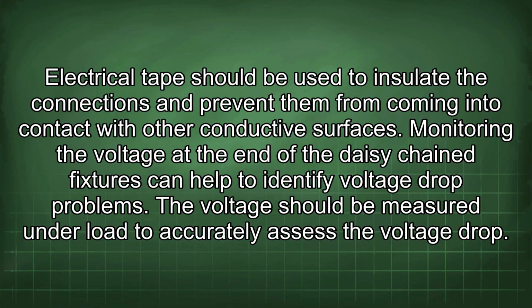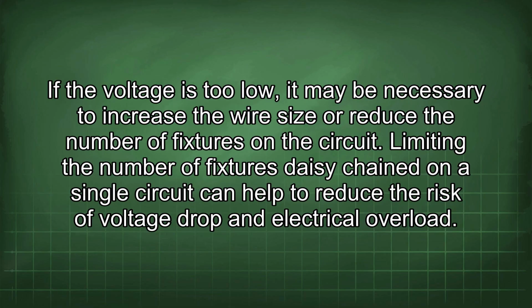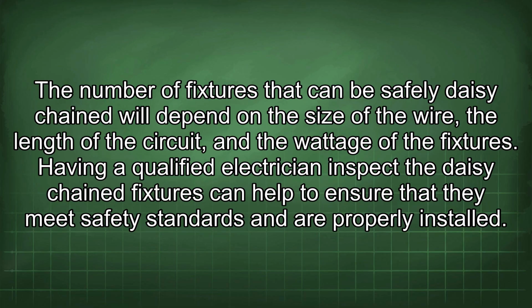The voltage should be measured under load to accurately assess the voltage drop. If the voltage is too low, it may be necessary to increase the wire size or reduce the number of fixtures on the circuit. Limiting the number of fixtures daisy-chained on a single circuit can help to reduce the risk of voltage drop and electrical overload. The number of fixtures that can be safely daisy-chained will depend on the size of the wire, the length of the circuit, and the wattage of the fixtures.